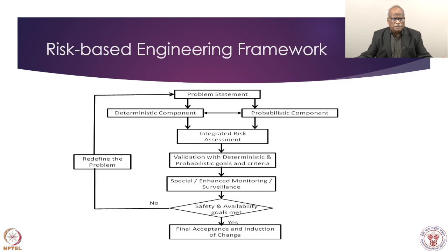So the deterministic component, as I said, we've been talking time and again, and the probabilistic component, they join hands together and give rise to the integrated risk assessment. Okay. And once we do that, we don't change any criteria or anything. We see whether the deterministic criteria and goal as it is, and the probabilistic criteria and goal, are being met. Say if a core damage frequency goal is 10 to the power minus 5, it should meet that whatever change you want to do. Okay.